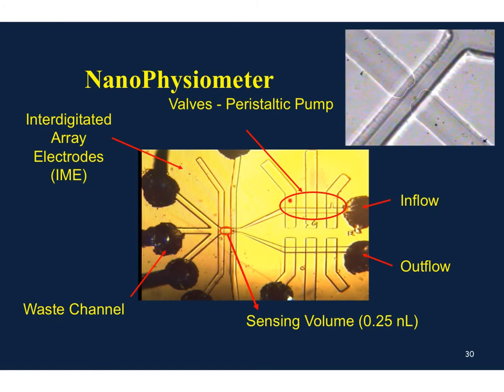These valves work like a peristaltic pump where you push fluid into each one in sequence, moving fluid along into the chamber, and you can do it in the opposite direction to pull fluid out. This is the sensing volume here, and these are the different waste channels.